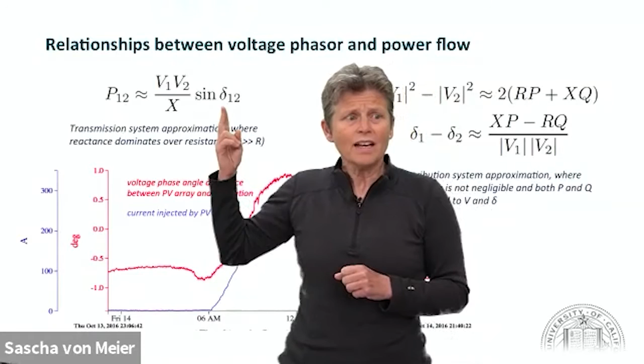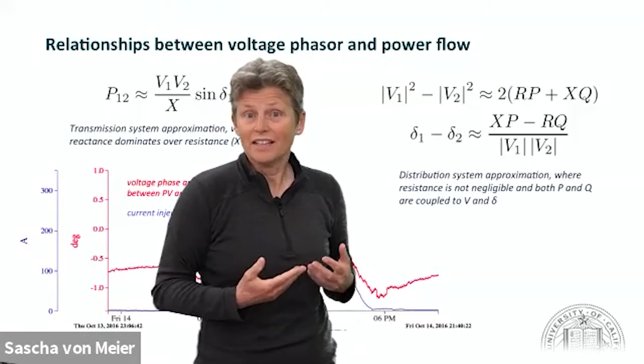So that's not always a good approximation for distribution lines, because by virtue of their smaller physical scale, the inductive reactance is not so dominant over the resistance. The resistance can play a big part. So a better set of approximations are these LinDistFlow equations, which relate voltage magnitudes to both resistance and inductive reactance, both R and X, and to real power flow P and reactive power flow Q, where the reactive power is the power that oscillates through the system in order to satisfy the time lags of inductive and capacitive devices that are everywhere.